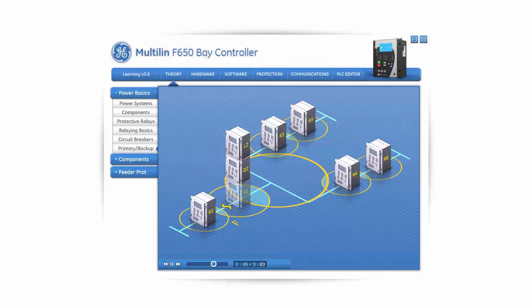However, let's assume that relay D2 of the duplicate system has also failed. The local backup relay L2 should now operate a short time after the primary and duplicate relays due to its coordination with them. If all three fail, the backup function of relays R3 through R6 is to provide remote backup to R2, D2, and L2.